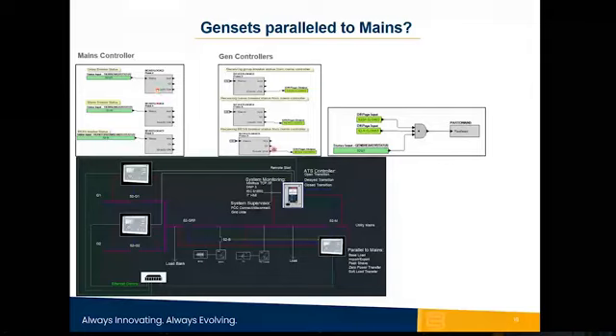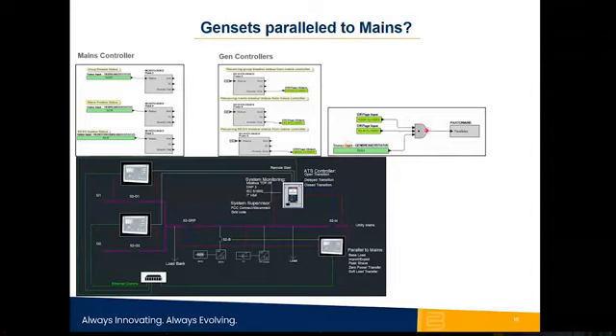Now we can take these statuses and determine whether or not we want to set the parallel to mains logic element. In this case, for instance, we're saying that generator breaker 1 is closed, mains breaker is closed, and group breaker is closed. So we have a continuous path to the grid right here, and we're setting parallel to mains. So therefore, we can parallel generator 1 to the grid in any of the 4 desired modes.